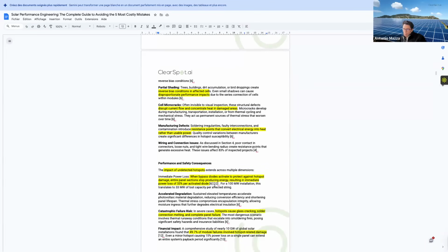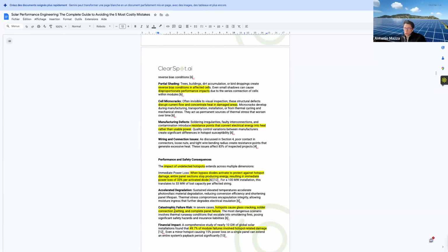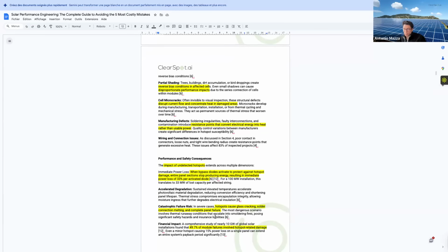So what are the impacts? I think this is one of the most relevant pieces of information you might take with you. Once bypass diodes start activating to protect against hotspot damage, an entire panel section can stop producing energy. This can directly and immediately produce a power loss of 33% per activated diode. For a 100 megawatt installation, that could translate to up to 33 megawatts of lost capacity per affected string. There is also an acceleration in degradation, and catastrophic failure risk can cause glass cracking, solder connection melting, and complete panel failure.